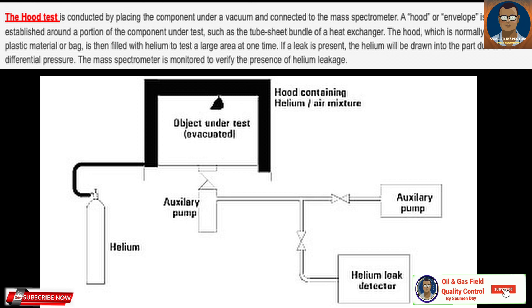The hood test, the third method, is conducted by placing a component under a vacuum and connecting it to the mass spectrometer. A hood or envelope is then established around a portion of the component under test, such as the tube sheet bundle of a heat exchanger. The hood, normally made of a plastic material or bag, is then filled with helium to test a large area at one time. If a leak is present, the helium will be drawn into the part due to differential pressure.